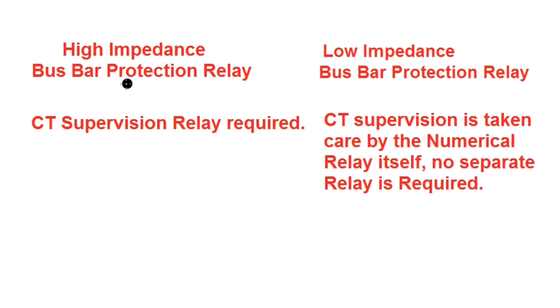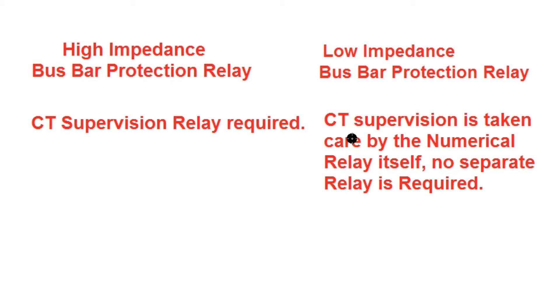In case of high impedance bus bar protection relay, a separate CT supervision relay is required for continuous supervision of the CT circuit. But in case of low impedance bus bar protection relay, no such separate CT supervision relay is required — the numerical relay will take care of the CT circuit supervision.